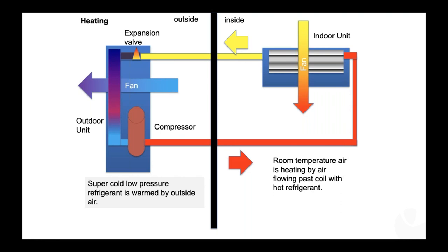It's attempting to get towards negative 30 or negative 40 degrees Fahrenheit, at which point it is certainly colder than anything that's going on outside. And so any of the heat energy that's in the air can get absorbed through the coil and into the compressor. Now, you might think, what the heck is he talking about, all the heat energy out there when it's 0 degrees or negative 10 degrees outside? Well, it turns out that the absence of heat energy is outer space, negative 273 degrees centigrade. When it's zero or even negative 10 or negative 15 degrees outside, there is not nearly as much heat energy as there is when it's 70 degrees outside, but there's still quite a lot. And that gas can absorb that heat energy.